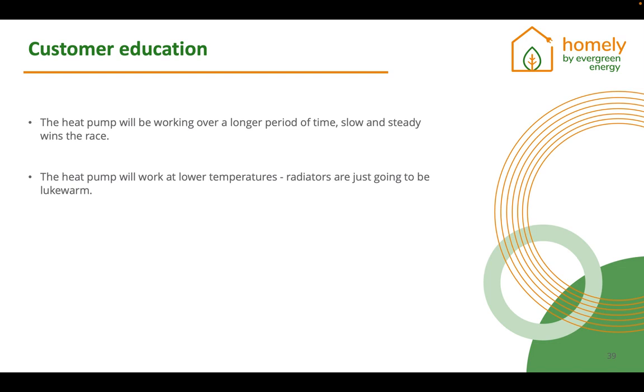But the most important thing to communicate before you go away from your installation is to tell the customer that the heat pump should be running almost continuously throughout the day. And that message of slow and steady wins the race is very, very important.